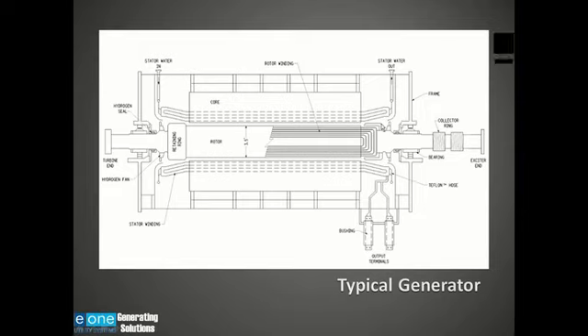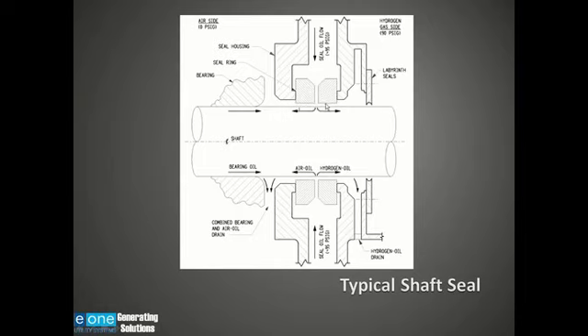As I mentioned, the difficulty with using hydrogen is sealing it inside the case. Here's a sectioned view of a hydrogen seal. How this operates is that I've got high pressure oil that is fed to the seal, and then the oil will go in the direction of the air because it's at a higher pressure, and it will go in the direction of the hydrogen because it's a higher pressure than the hydrogen. You can see that the oil pressure is 95 psig, whereas the hydrogen pressure is 90. So the oil will flow towards the hydrogen, flow towards the air, and that will create a seal around the oil, keeping the hydrogen inside the generator.